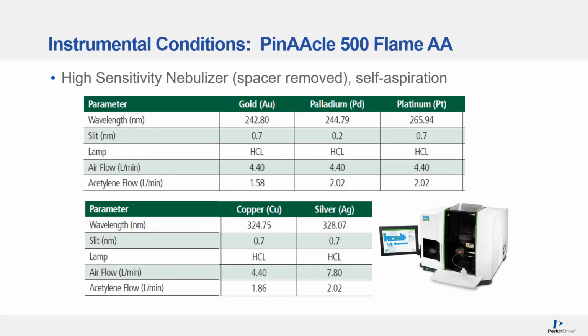To show you what the conditions were on the PinAAcle 500 for this test, here are two tables describing what wavelengths, slits, lamps, airflow, and acetylene flows were used. Now for all these tests, we were using a high sensitivity nebulizer with the spacer removed, and we were using self-aspiration, not an autosampler. For all these metals, not just gold, we are actually optimizing the flame conditions, so the gas flows, both the airflow and acetylene, to maximize our signal and stability.